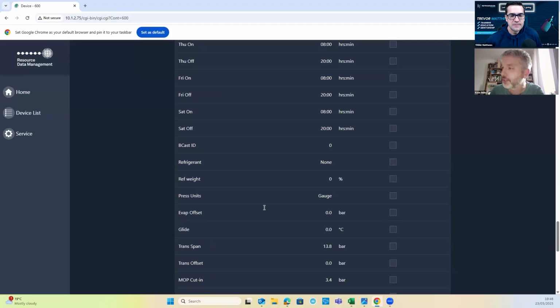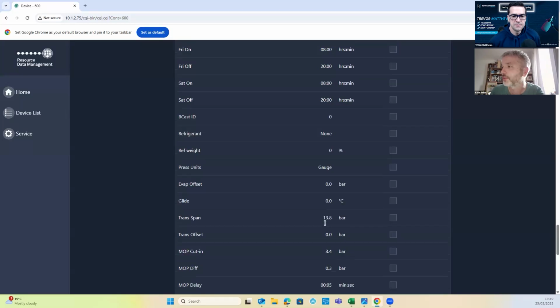So, when you're coming to set up your transducer, a bit like we talked about previously, all your transducer parameters are right here. So you can set a refrigerant type. Ref weight, it explains in the manual. Nobody should need to change that normally. Evap offset, it's from the reading that you're getting for pressure drop? Is it an HFC that's got glide? Do I need to set glide in there? And then you've got your basic transducer span and offset, as we discussed on the last one.